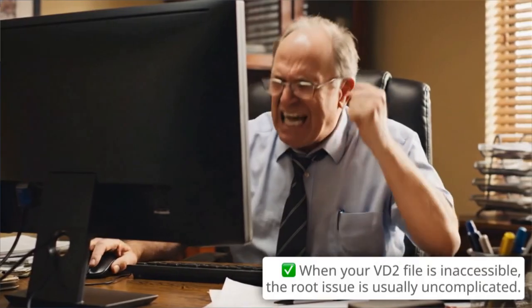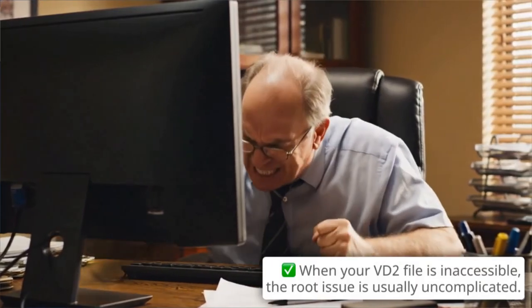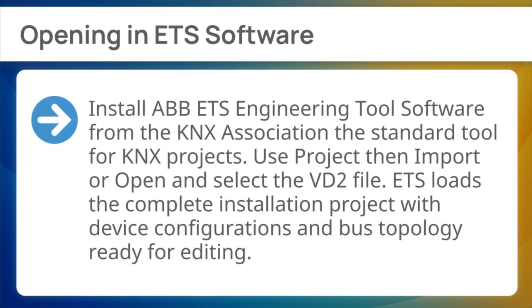Before we proceed, let's run through this short checklist to confirm key parameters. First, opening an ETS software. Install ABB ETS engineering tool software from the KNX Association, the standard tool for KNX projects. Use project, then import or open, and select the VD2 file. ETS loads the complete installation project with device configurations and bus topology ready for editing.